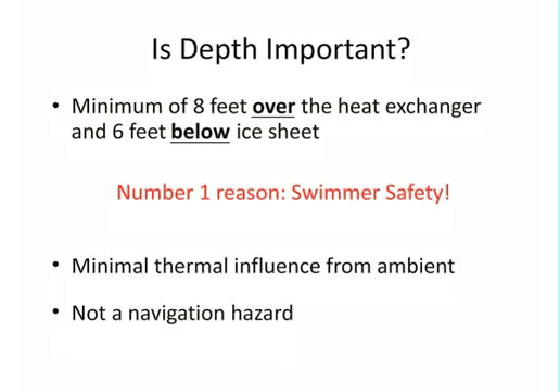Consider that you may have a body of water with a lot of recreational activity, so you want to make sure the heat exchanger is at a depth where swimmers can't get to it. You don't want a tragic result of someone getting tangled up in it. The other reason for depth is minimal thermal influence from ambient air temperatures, one of the significant advantages of pond loops. Obviously we also want depth so we don't become a navigation hazard.